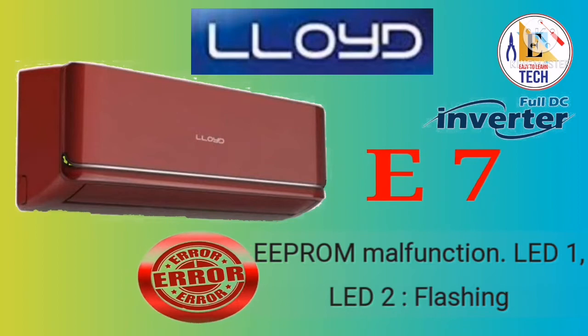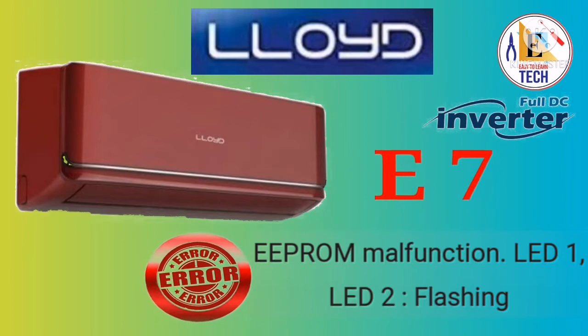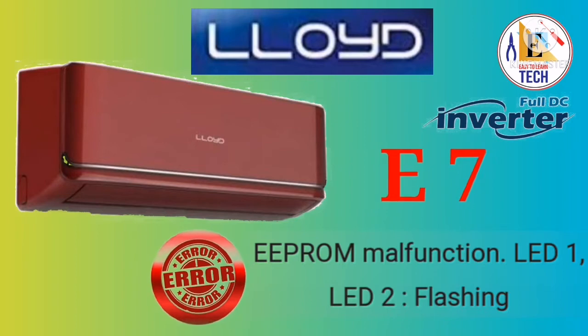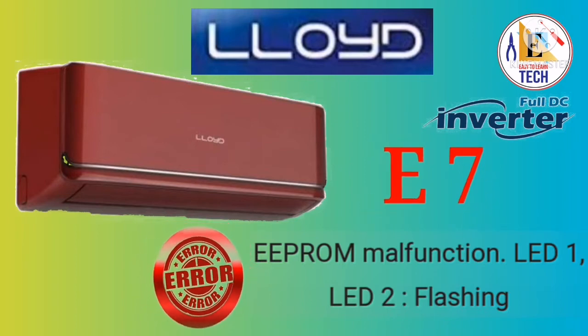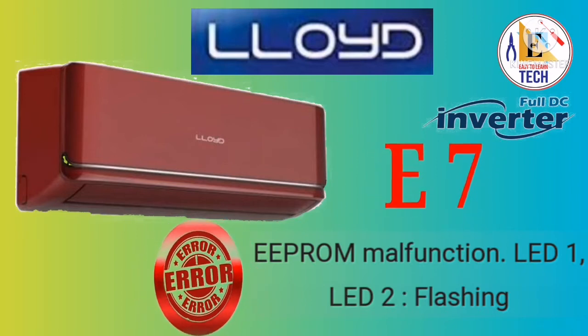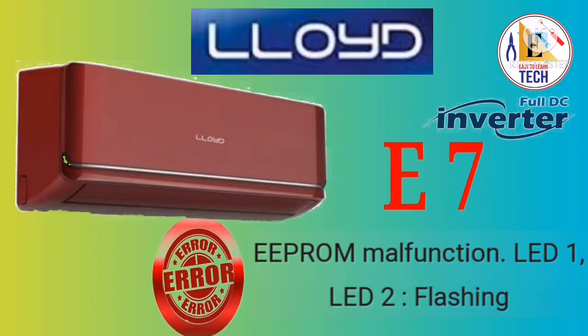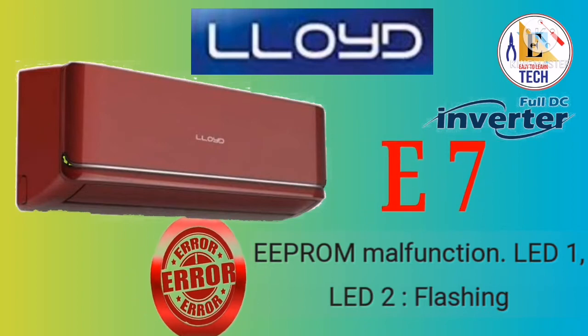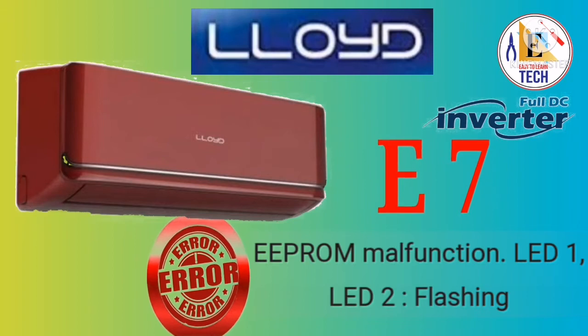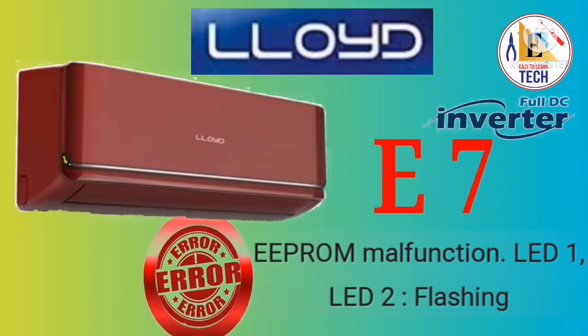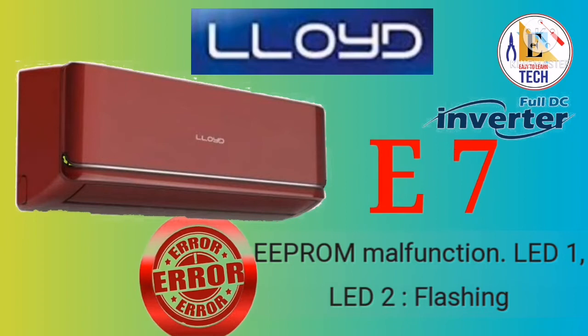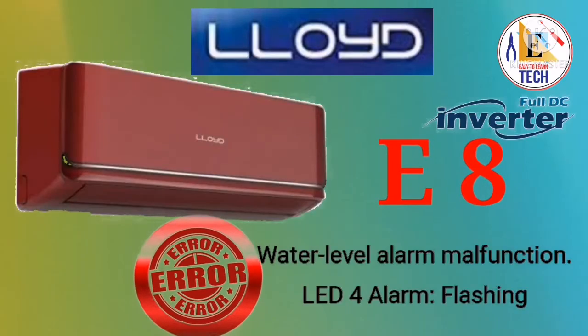When you see E7 in your display, it means EEPROM malfunctioning, or you can see LED1 and LED2 flashing. It also means EEPROM malfunctioning. First of all, you have to check in your PCB if the EEPROM is removable or not. If the EEPROM is not removable, then you have to replace your whole PCB card. If the EEPROM is removable, then you have to bring the same model EEPROM and reinstall it. You have to check if you get the solution for this error. Most of the time, if you get this error E7, you have to replace the PCB and you will get the solution for the error E7. Let's see the next error code.